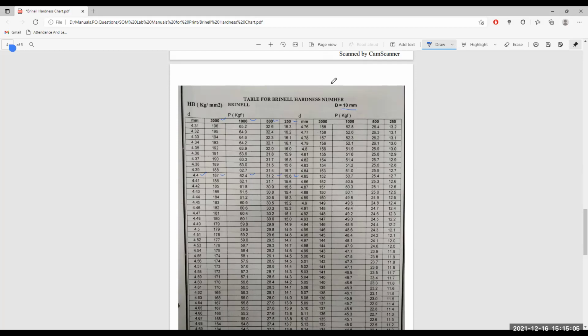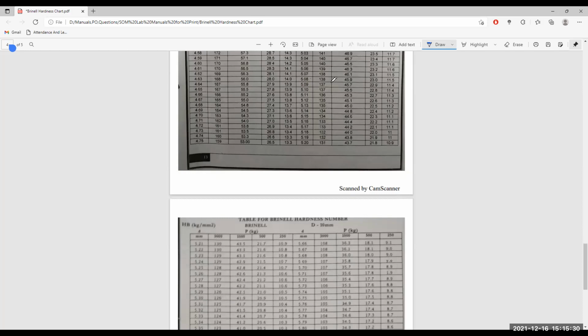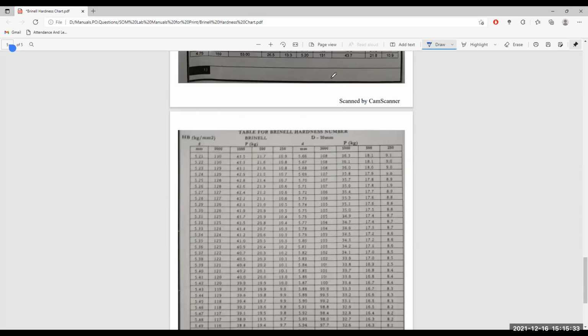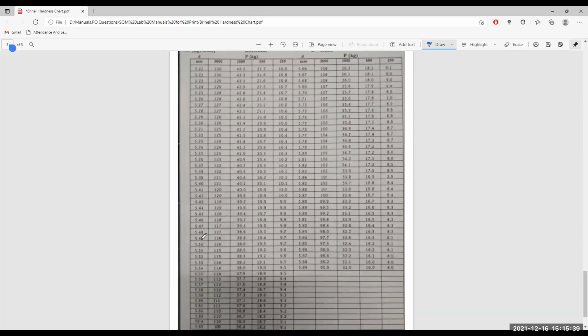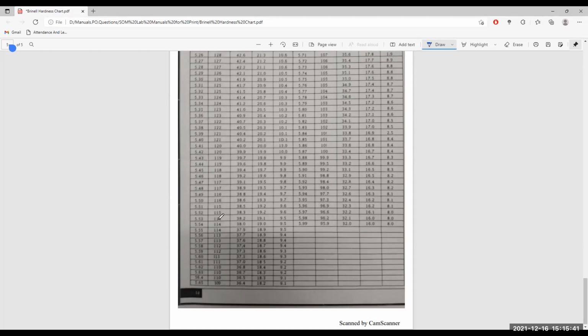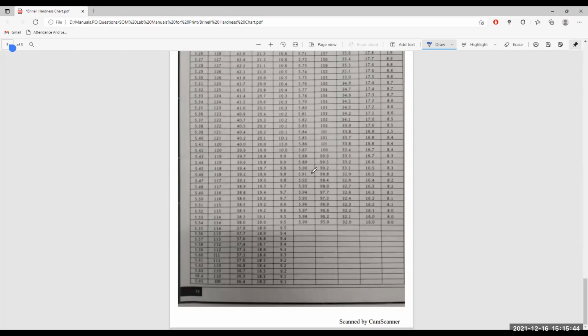Here also, say a 5.00 millimeter diameter. For an applied 3000 kg load to make this diameter, the hardness is 143. For applying 1000 kg, it is 47.5. For the applied 500, it is 23.8, and for the applied 250, 11.9. This is the method of relating the indenter load with the hardness. The same procedure is going on: the higher the size of the impression, the lower the hardness, for applying different loads.